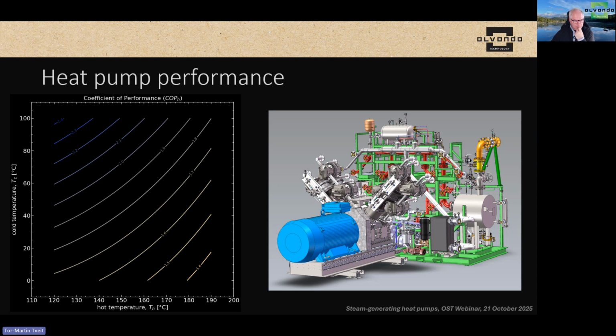We also have applications running on different temperatures at different times. We have one case in the Netherlands, at a dairy facility, where they have a heat source normally at around 85 degrees. But from time to time, when that heat source is not available, they have another heat source around 30 degrees. The heat pump just switches between the heat sources, and you don't need to do anything else than adjust some temperature ranges in the control system. That application is generating steam at around 150 degrees, I think around 3.5 bar.